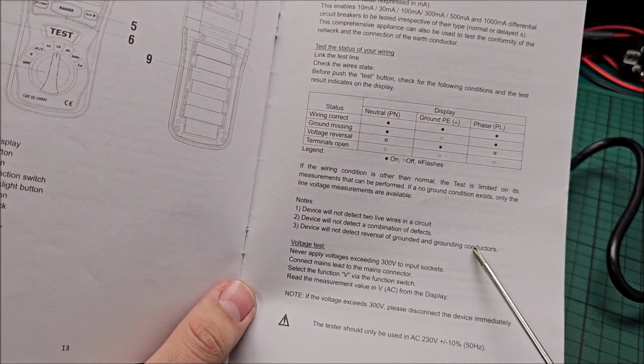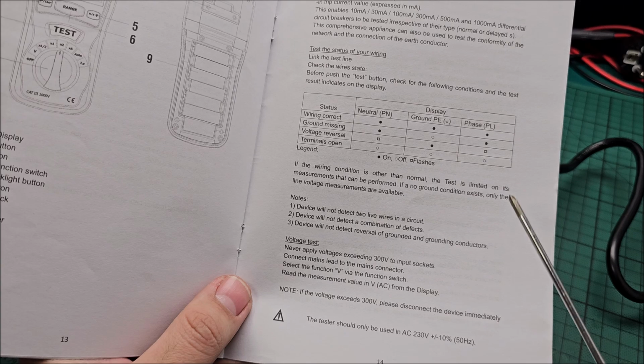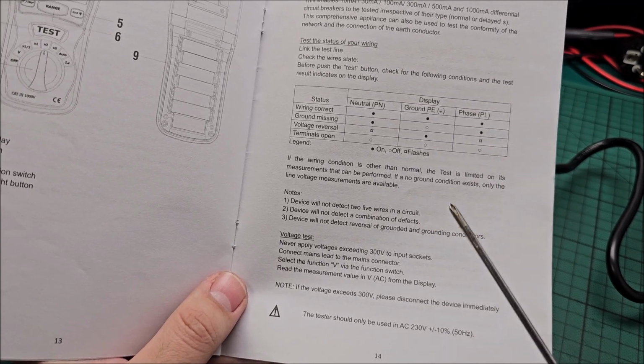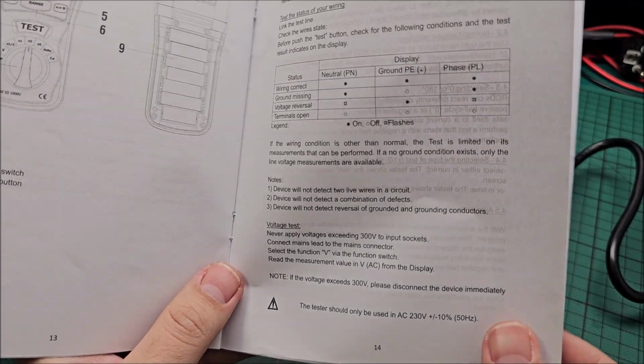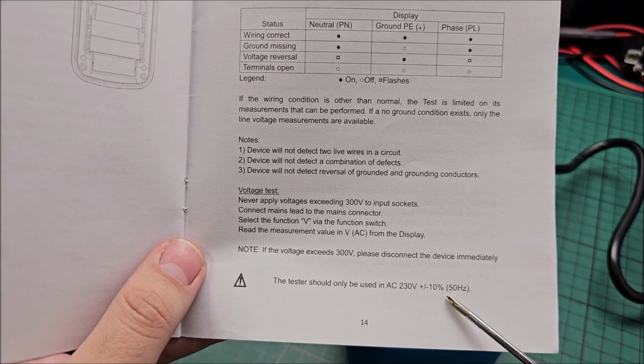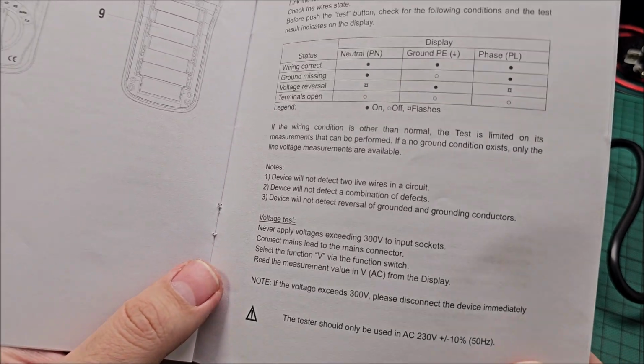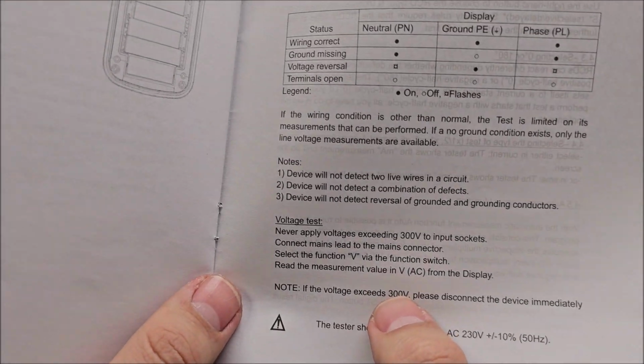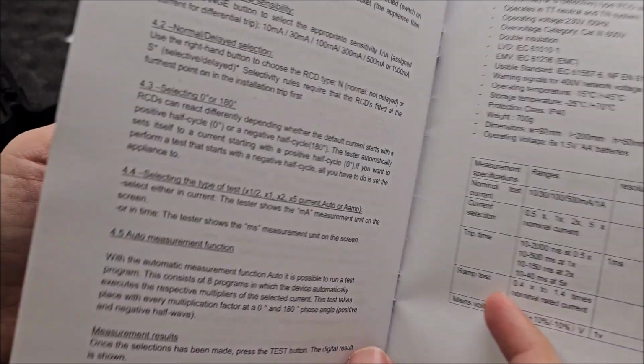It's telling us that this is not really meant to detect other problems in your circuit. This is for RCDs. You can see here plus minus 10%, and at 50 Hertz the frequency. Don't use higher than 300 volts.